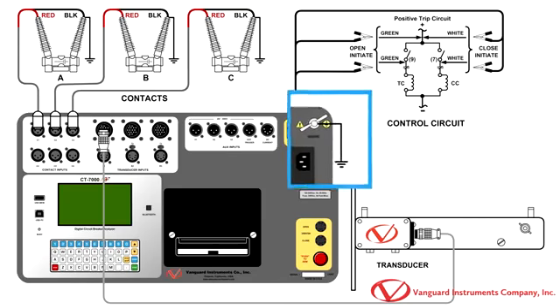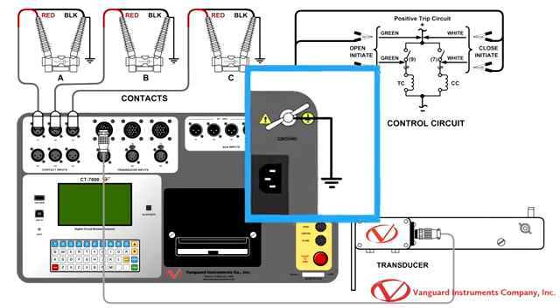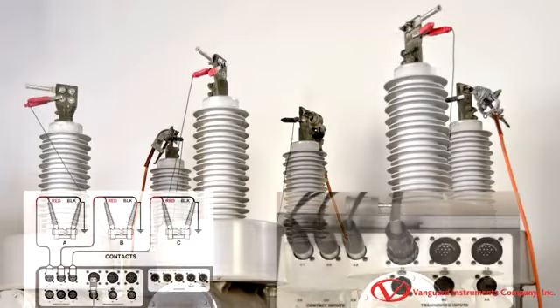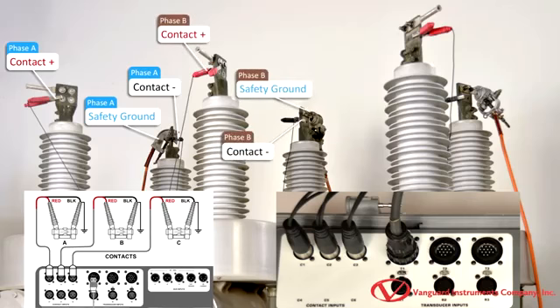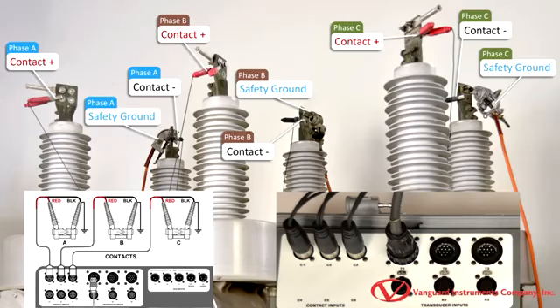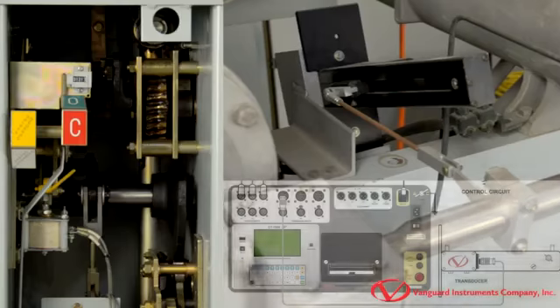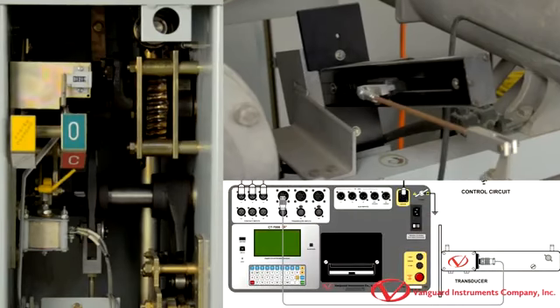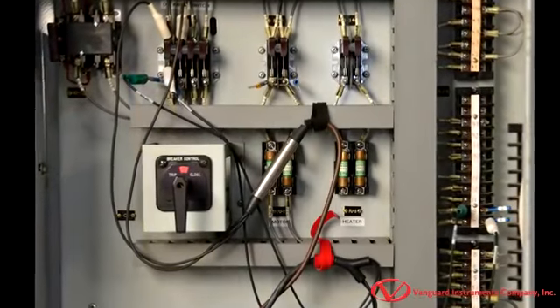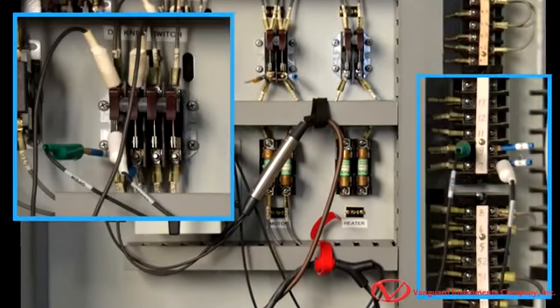First, start by connecting the CT7000S3's ground terminal to the substation ground. Now, connect the contact and ground cables for each phase being tested as shown here. Next, we will connect the digital transducer to the CT7000S3 as shown here. Then, we will use the supplied initiate cable to connect to the breaker's control circuit.